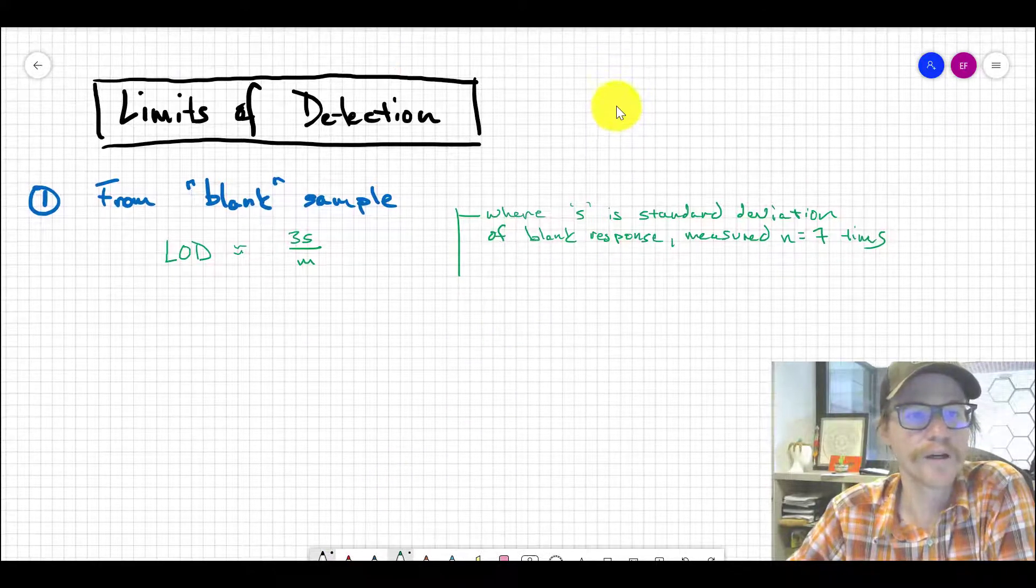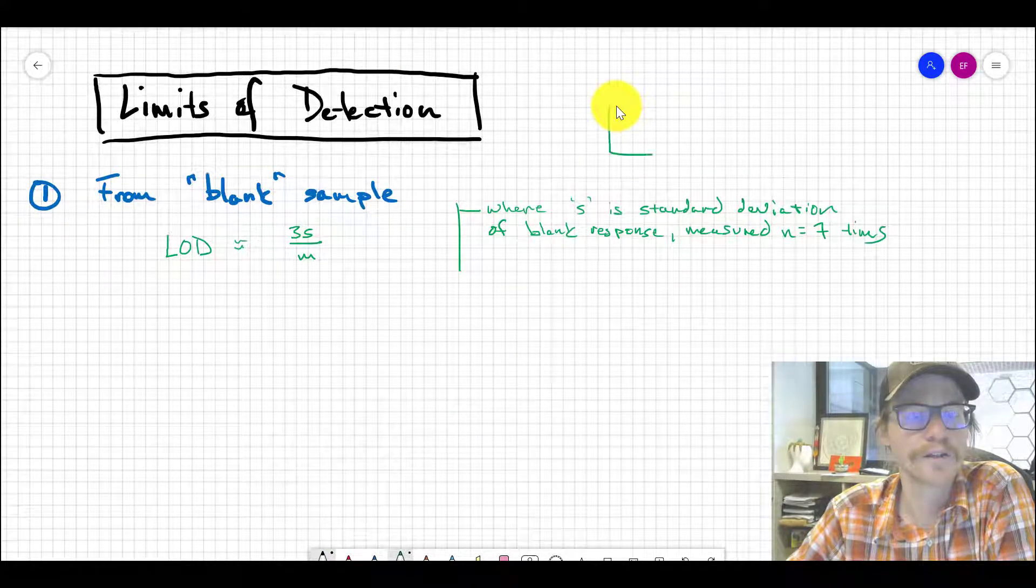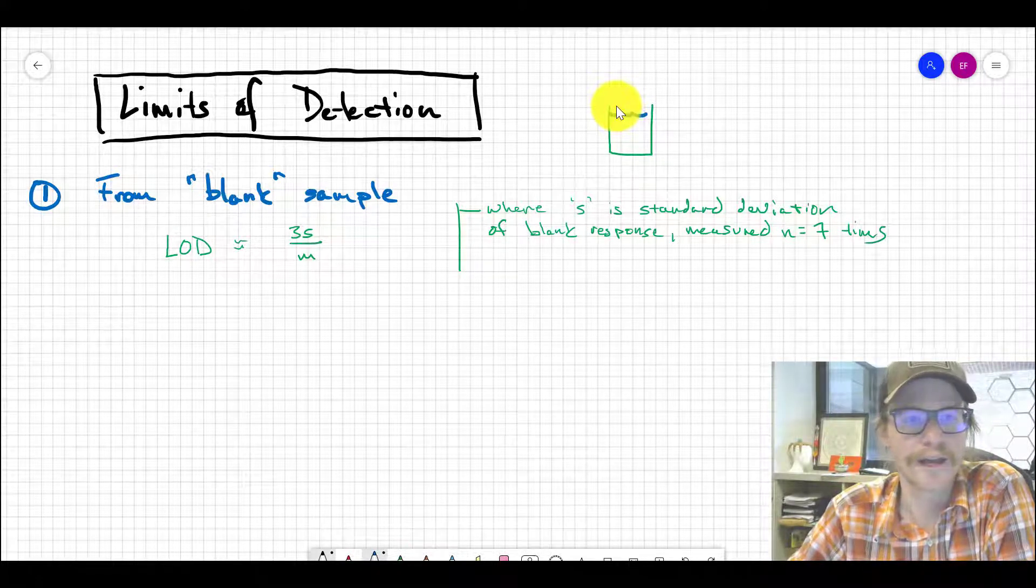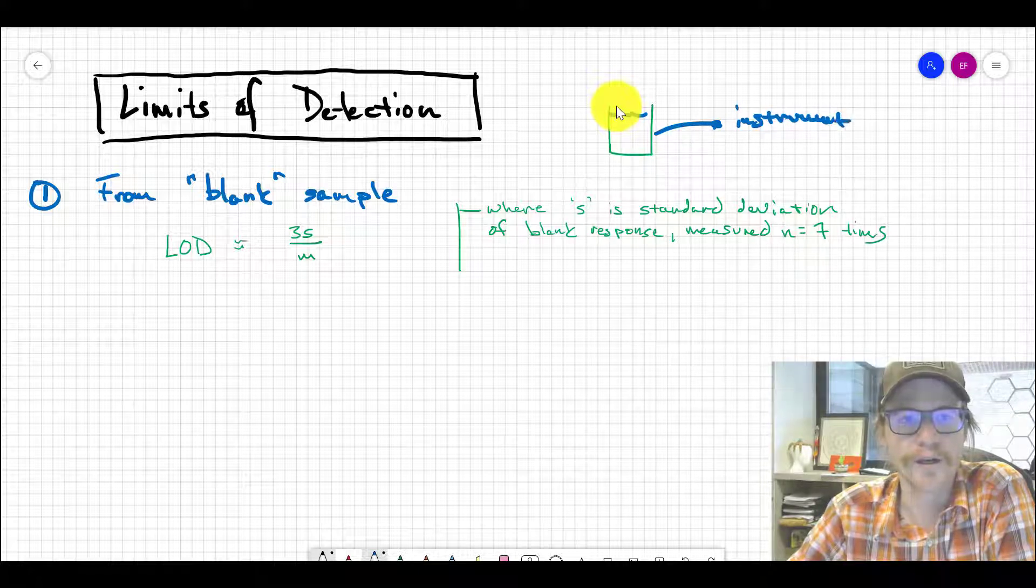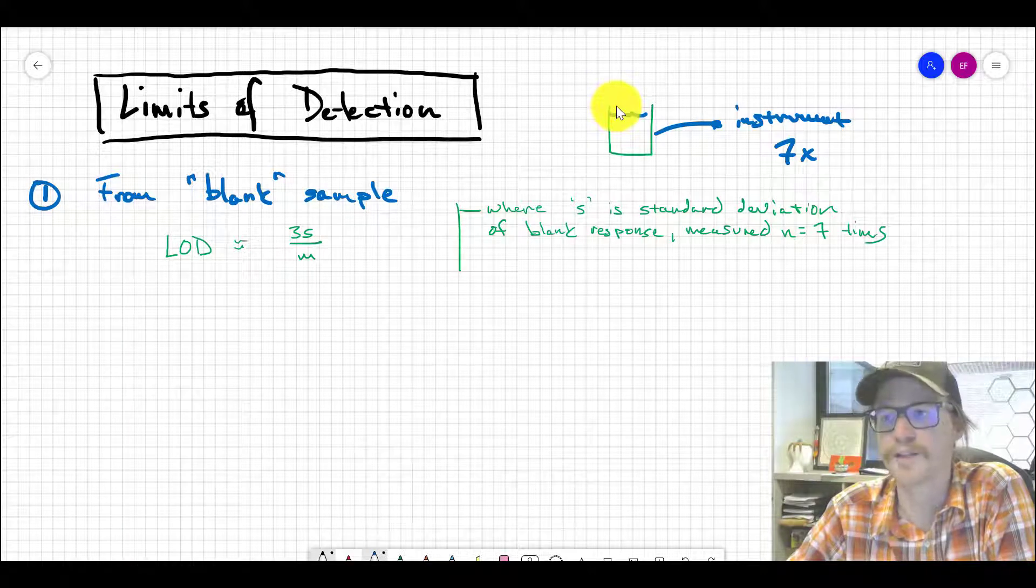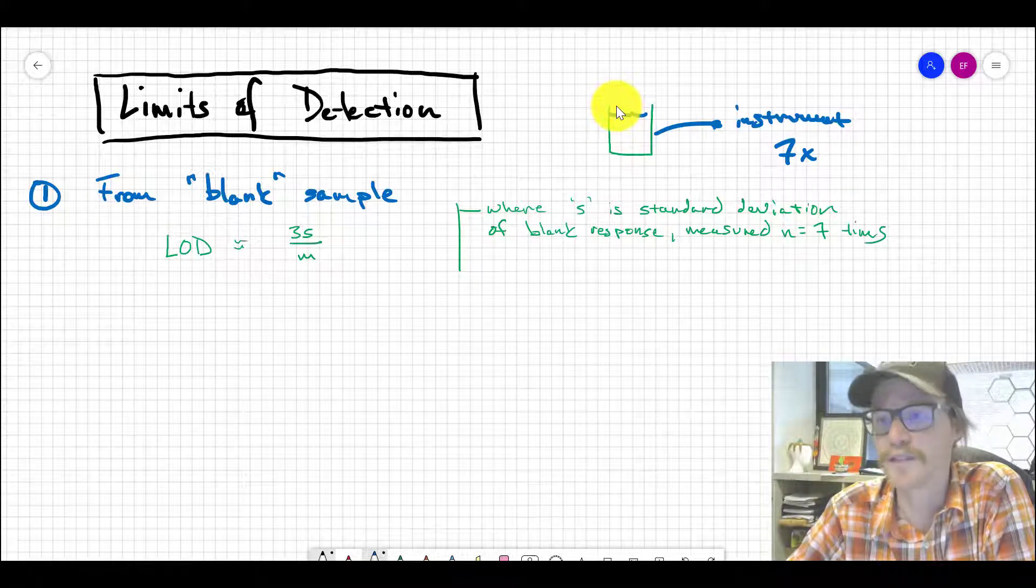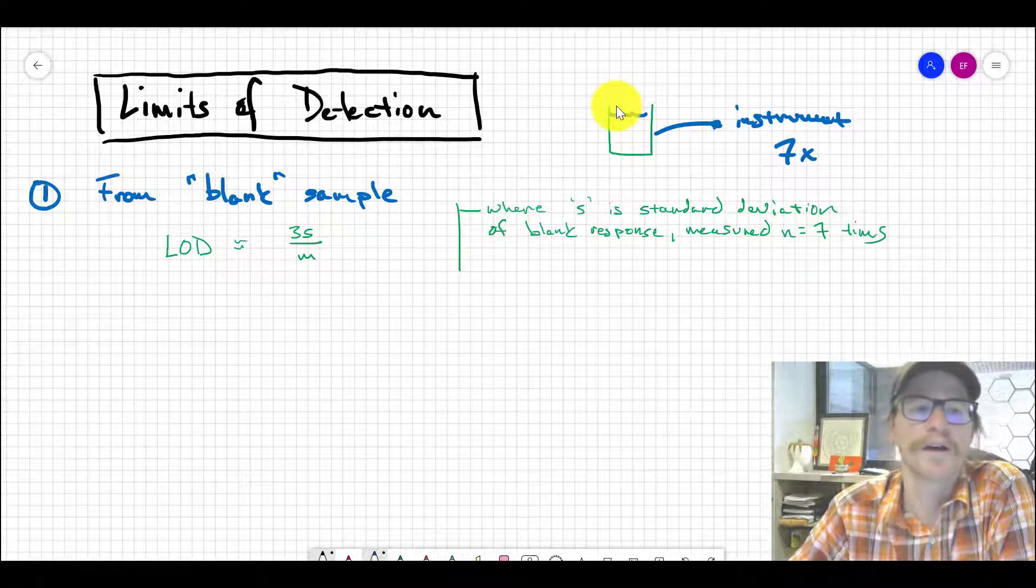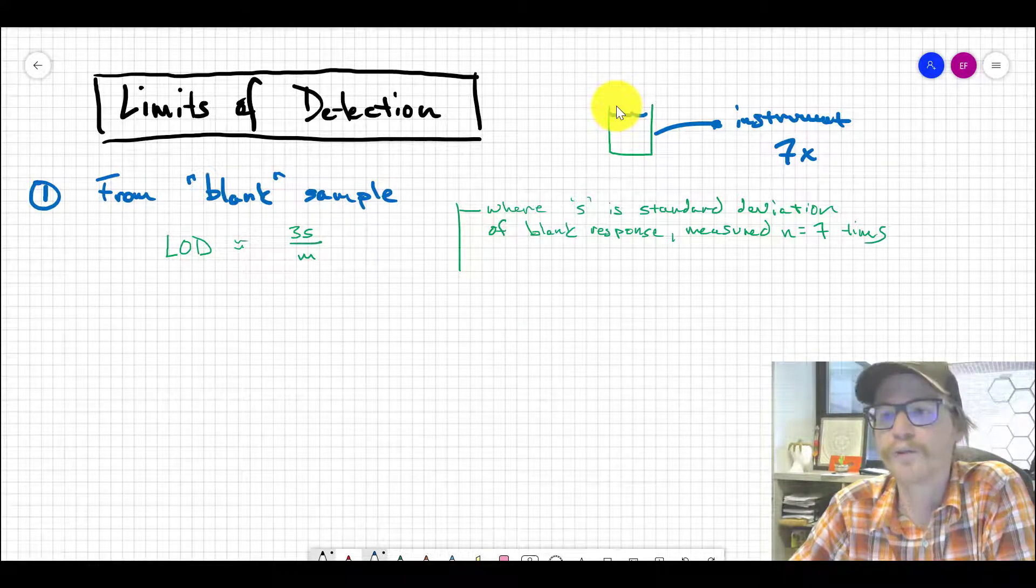You'll take that blank solution and put it into your instrument. You're going to measure it seven times—the same exact blank—which gives you seven measurements. You'll take the standard deviation of those measurements and compute...